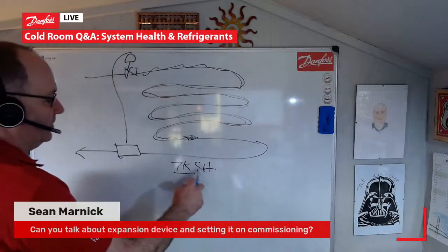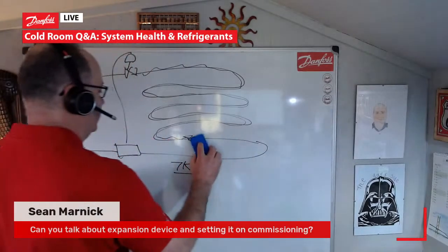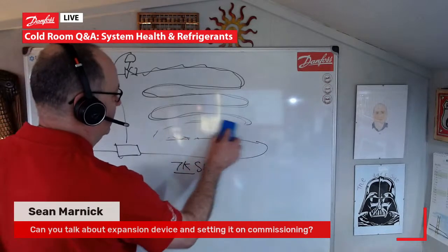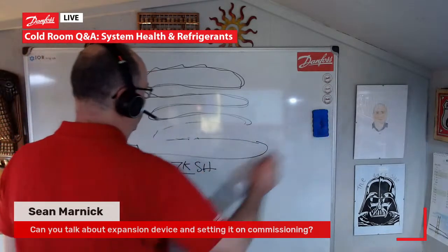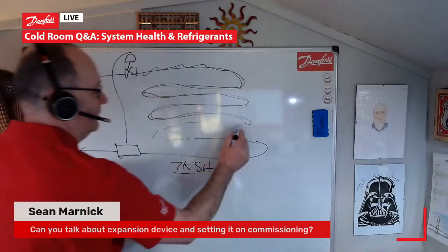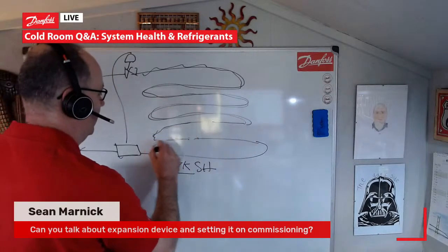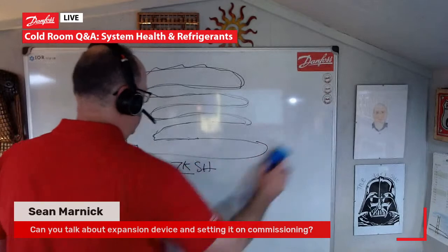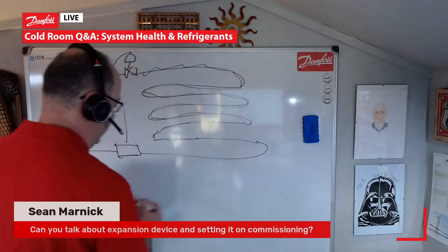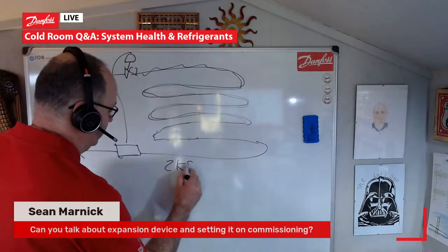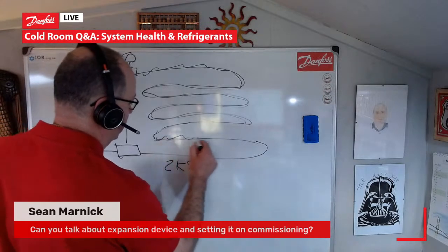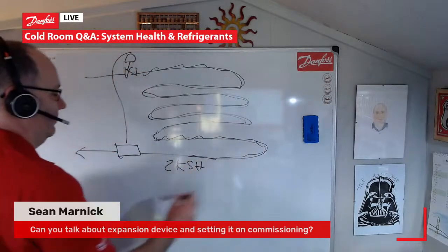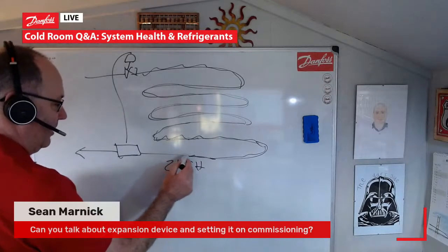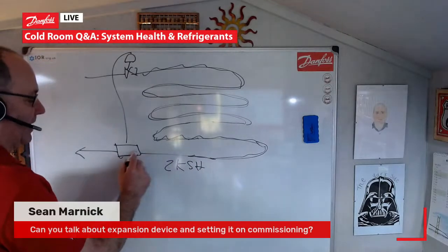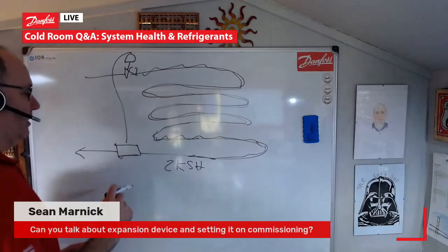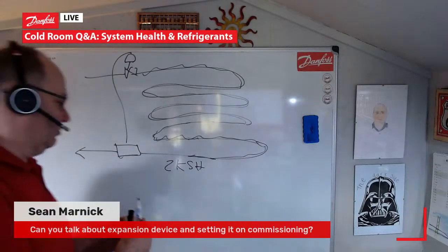If we have a very high superheat, basically what it means is that the part of the evaporator that we are utilizing gets smaller, so that we don't get the same amount of duty or capacity from that evaporator. If we've got a very small superheat, let's say we had 2K superheat, then we would be utilizing maybe that much of the evaporator. And then we've got to be very careful, because we could have liquid coming back down the suction line to our machine, which is not good. We don't want to break the compressor.